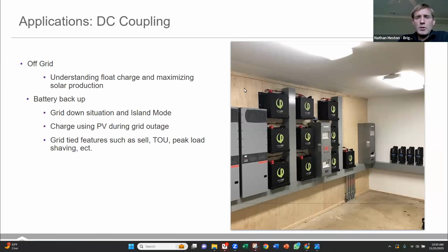With battery backup situations, a lot of customers want to just not lose power when the grid goes down. Maybe it's important to you to stay connected. In my case, I don't want to lose power if the grid goes down. I want to make sure that my internet stays there, and so it's important to have that battery backup for those reasons. Other customers want to be able to keep that solar going when the grid goes down. You can now use PV to charge during a grid outage with your DC coupled system.